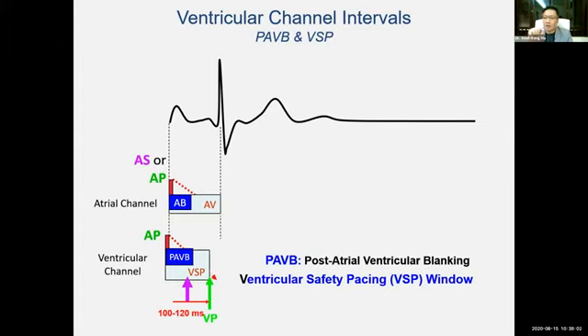Now, this is especially important for those patients who are dependent on pacemaker at the ventricular level, for example, complete heart block. If you have an event detected at the ventricular level, although it falls into the ventricular refractory period, it must be handled with care, because if you see it and then you think that this is just another intrinsic cardiac activity which you ignore, you may, at the end of the refractory period, pick up another signal that initiates another timing cycle, so the pacemaker won't pace at the ventricular level. As you know, if the patient is pacemaker dependent, this will be catastrophic for the patient.